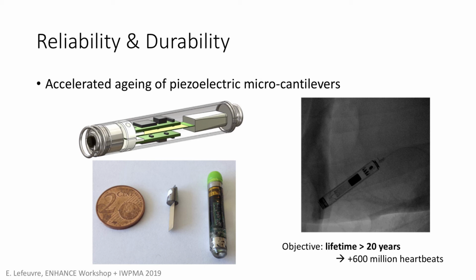And this is an X-ray image, real time, where you can see the capsule with the cantilever beam inside. I don't remember if it was the heart of a sheep or a pig, but an animal with a heart of the same size, similar to the human one. So the objective is more than 20 years operation of the device, which means approximately 600 million heartbeats. And if you have a resonance system, you will have, of course, a multiple of these 600 million heartbeats in terms of oscillations.